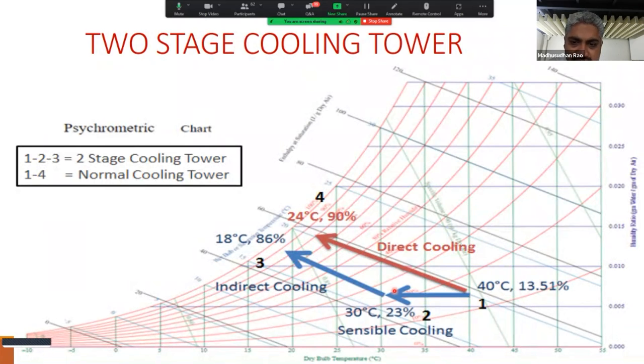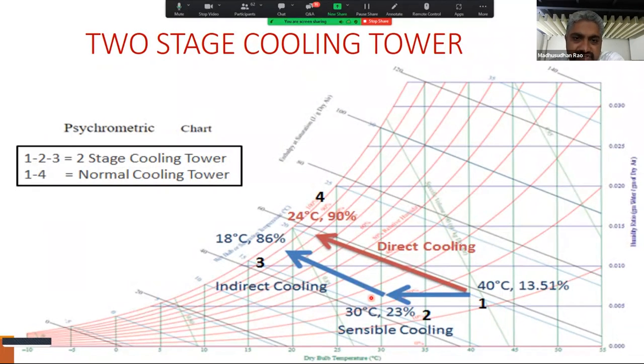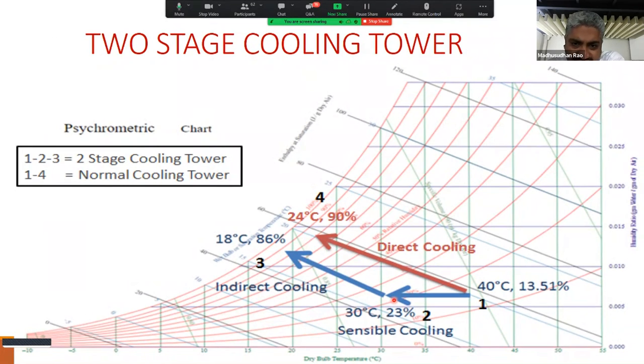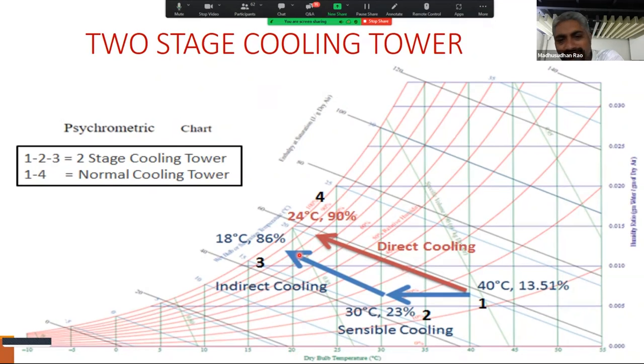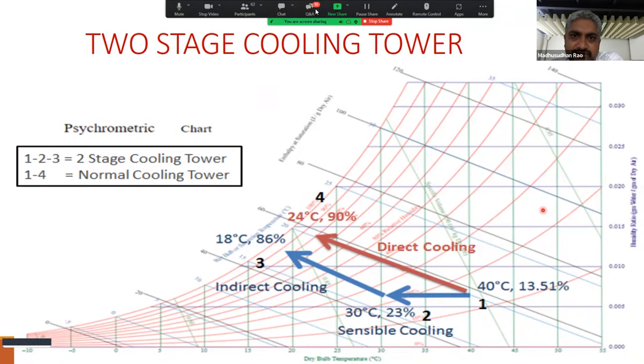It's sensible cooling. Now, if initially we were getting 24 degrees centigrade, we can get air now at 30 degrees centigrade. Its RH has increased, but its wet bulb is now lower, maybe around 17 or 16 degrees, something like that, maybe lower, right? Once this air goes inside the cooling tower, it will deliver lower temperature water, because its wet bulb is lower now, since you have changed the psychrometrics of the air. Now you can do it in multi-stage. There are other ways to do it. So basically this is just a two-step. You can play around with it and do much better and get lower temperatures. So I hope I've answered that question.